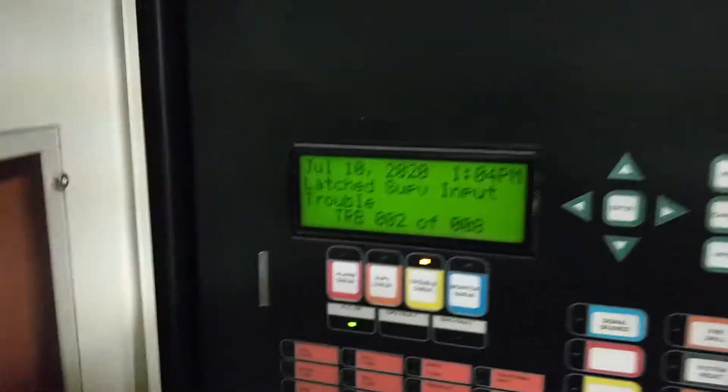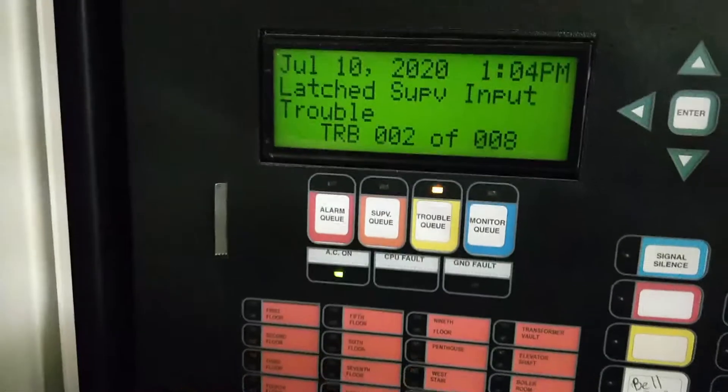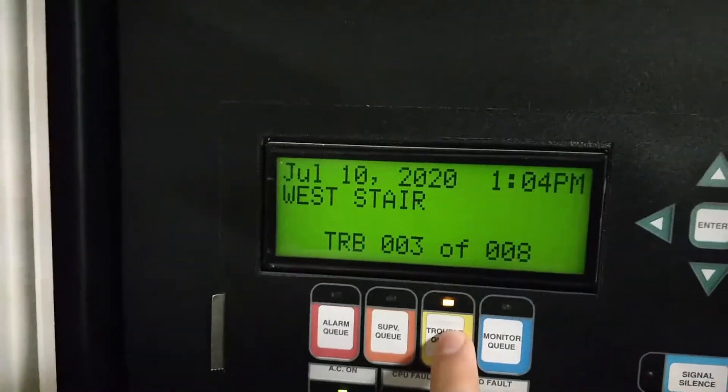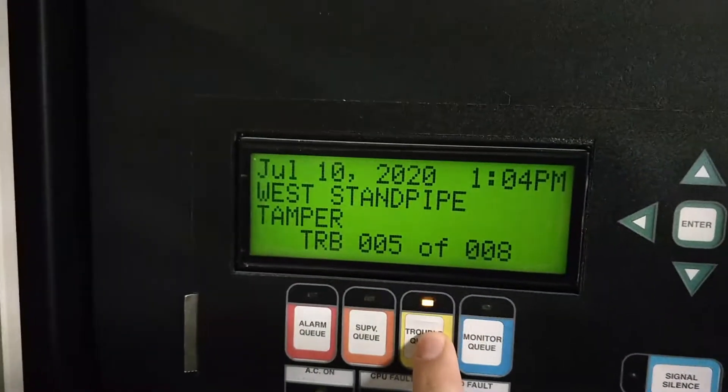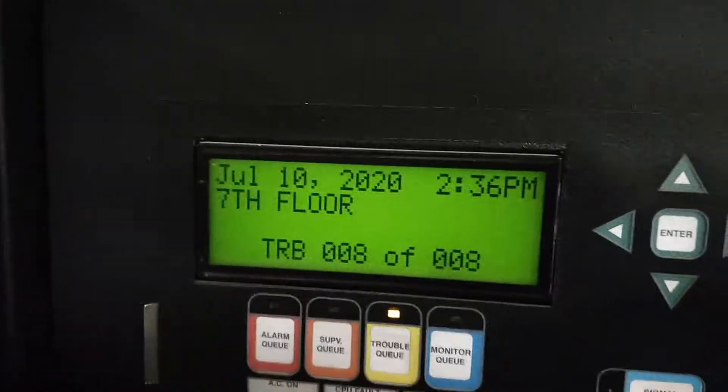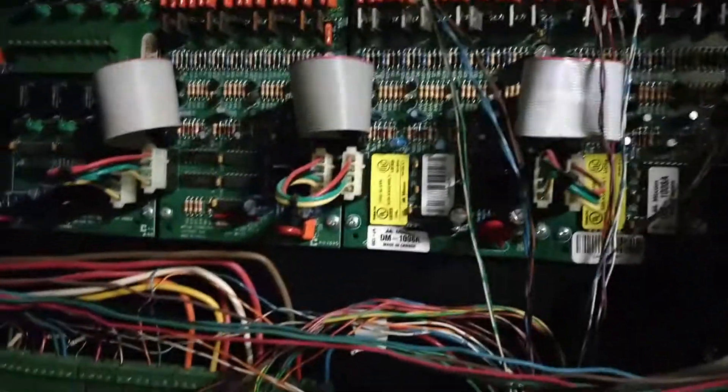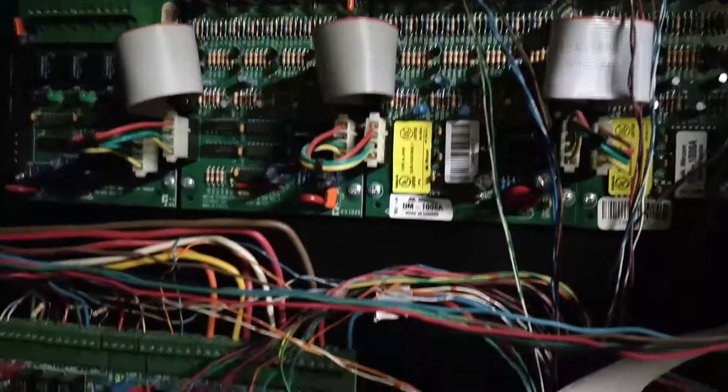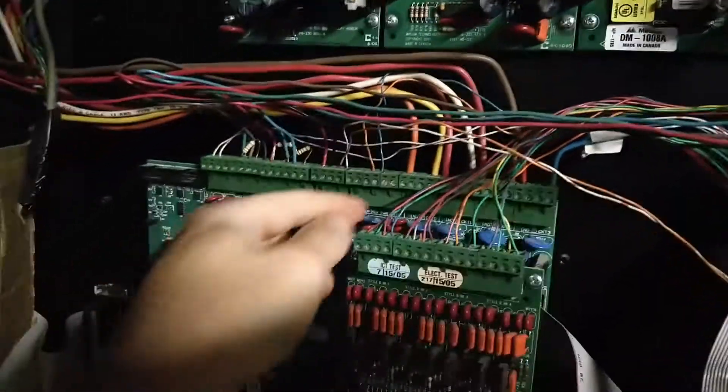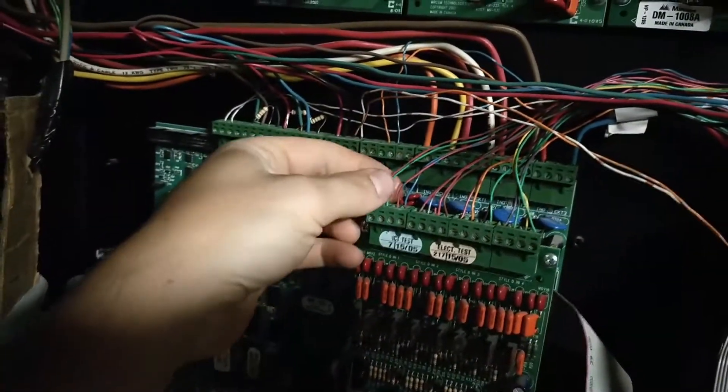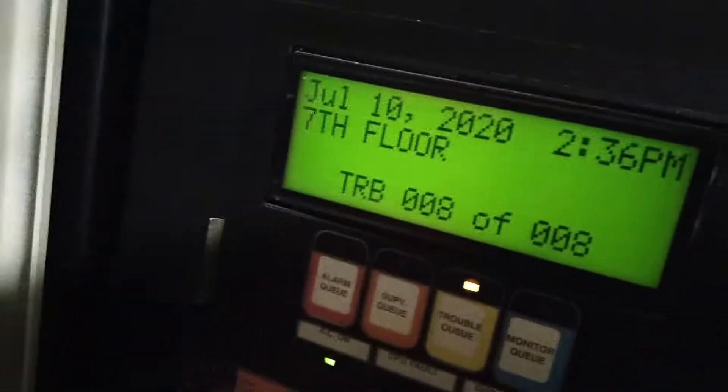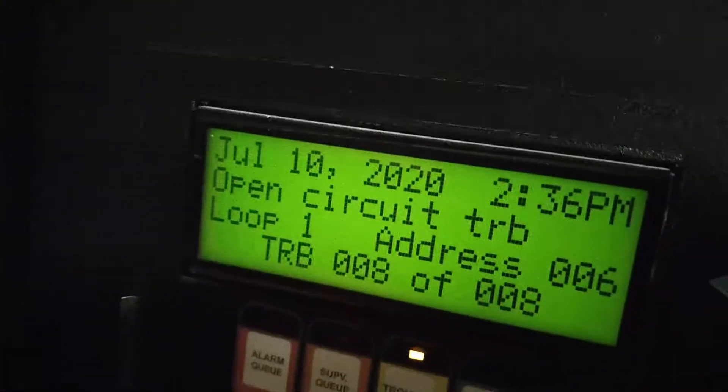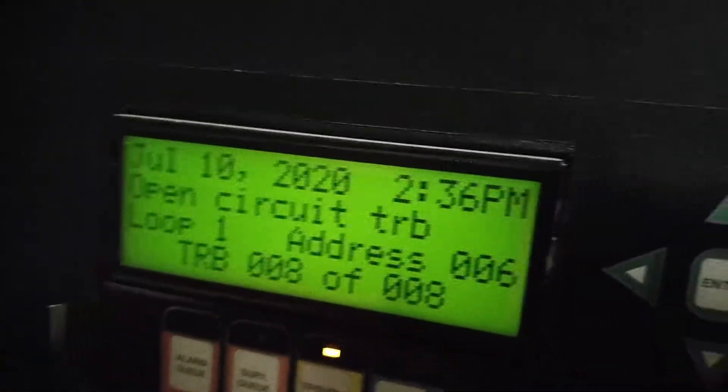Okay, so we've got all kinds of stuff going on here. This panel is showing opens on all kinds of zones. The interesting thing is you meter the wires and they've got a clean end of line, 3.9. You can even pull them out of whatever zone is showing open and put in a resistor right in it and it doesn't clear.